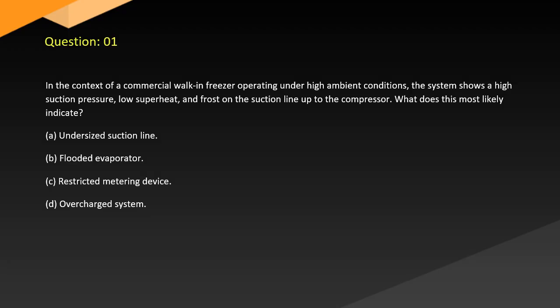Question 1. In the context of a commercial walk-in freezer operating under high ambient conditions, the system shows a high suction pressure, low superheat, and frost on the suction line up to the compressor. What does this most likely indicate? A. Undersized suction line. B. Flooded evaporator. C. Restricted metering device. D. Overcharged system.